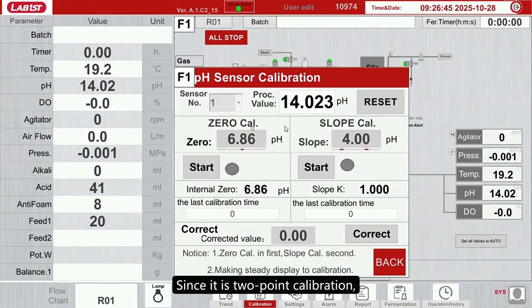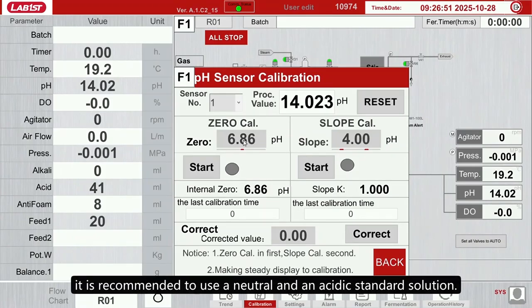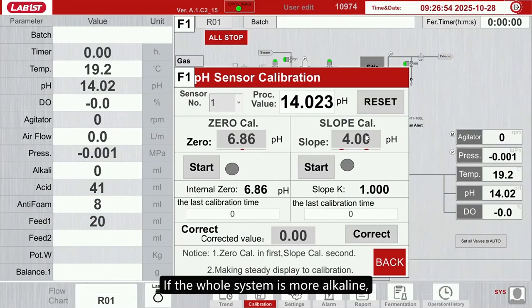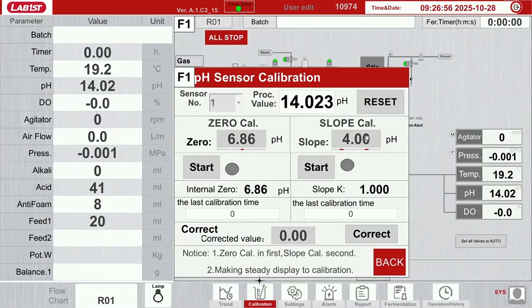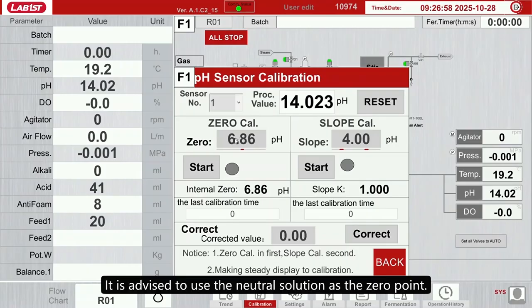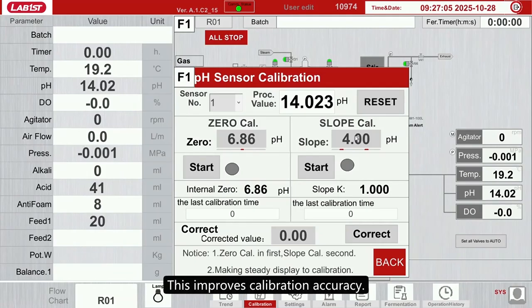Since it is 2-point calibration, if the whole system is more acidic, it is recommended to use a neutral and an acidic standard solution. If the whole system is more alkaline, it is advised to use the neutral solution as the 0 point. Then an alkaline standard solution serves as a slope. This improves calibration accuracy. Slope will be displayed. It will also show the last calibration time.